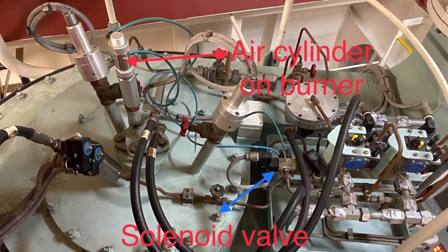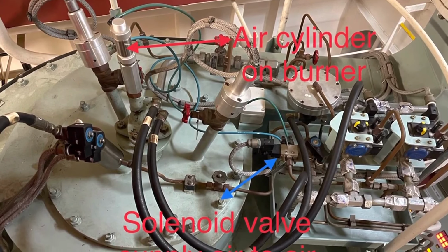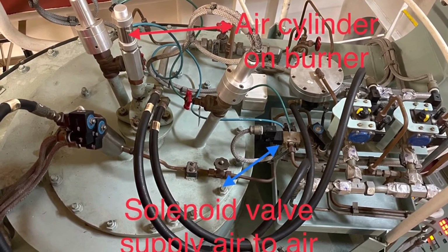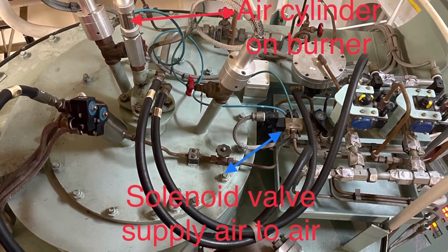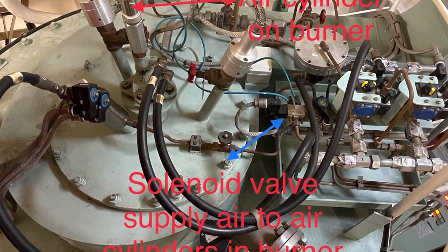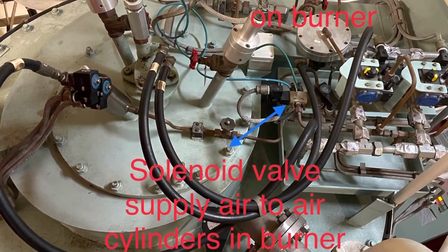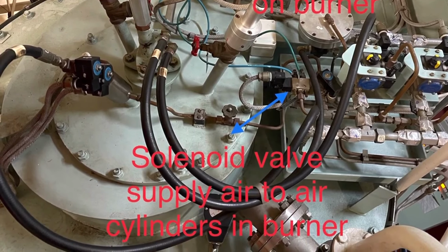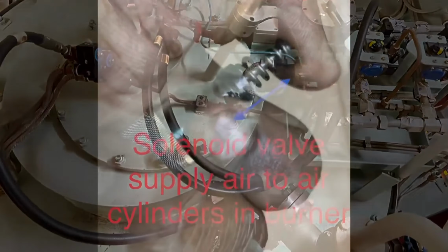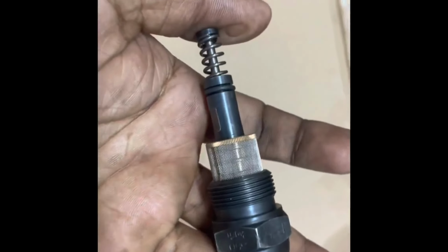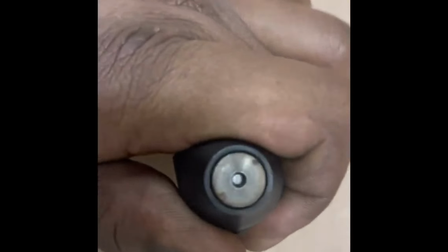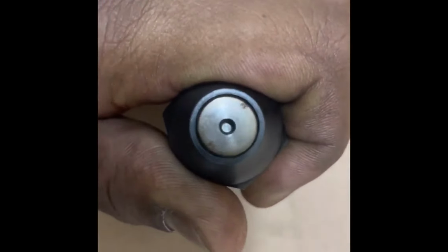The solenoid valve supplies air to the air cylinder in the burner, which I mentioned earlier, which is used to block the oil nozzle after shutdown to protect the environment from possible oil pollution. You can see the spring action on this nozzle. By pressing it, it is blocking the nozzle, which is exactly what the air cylinder is doing.